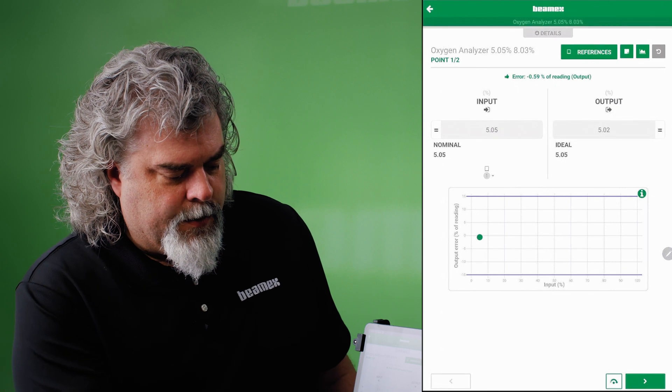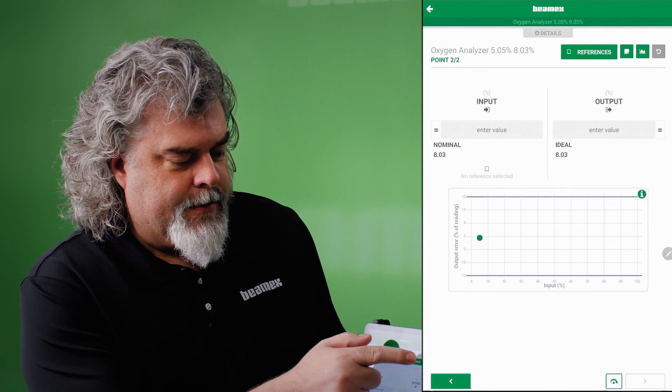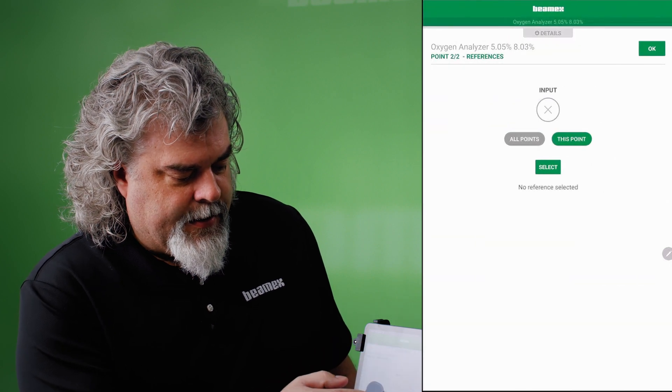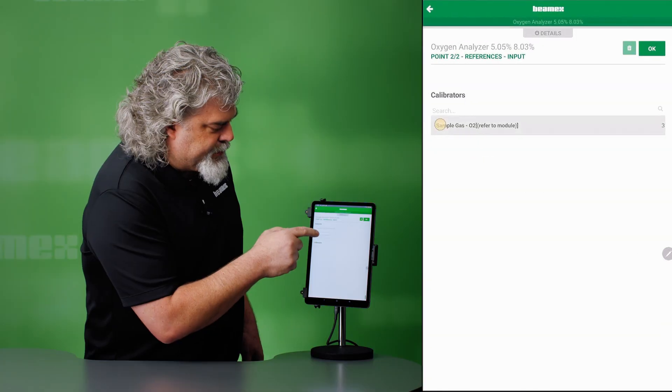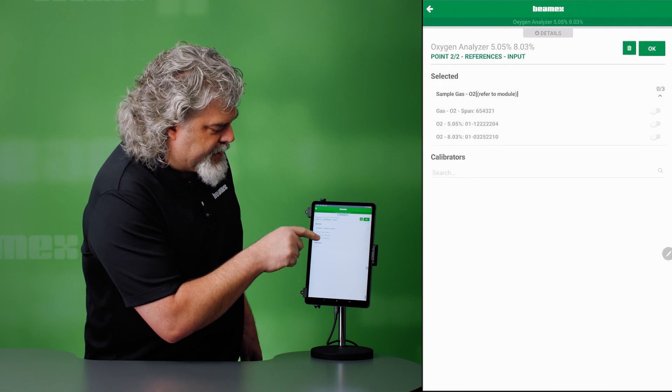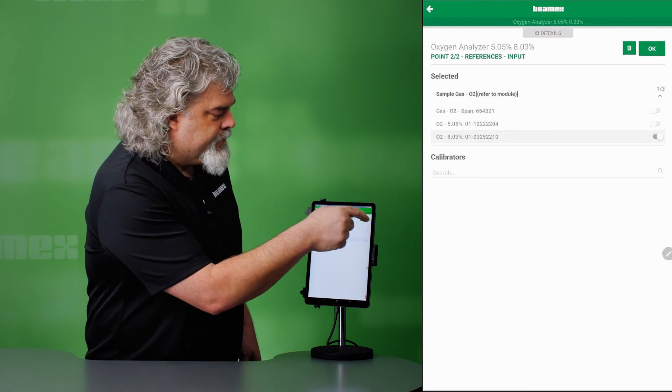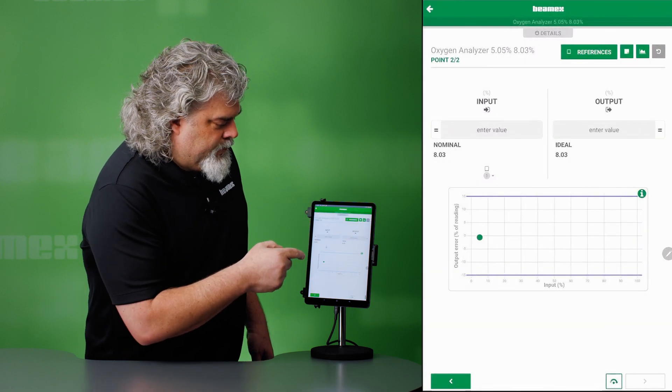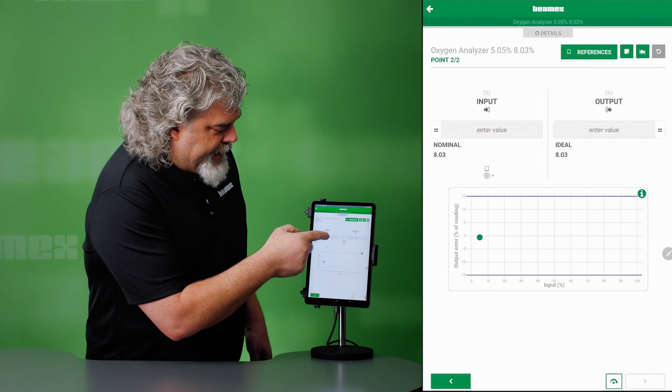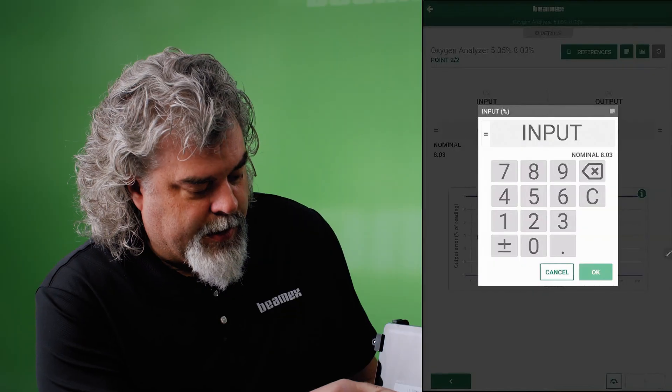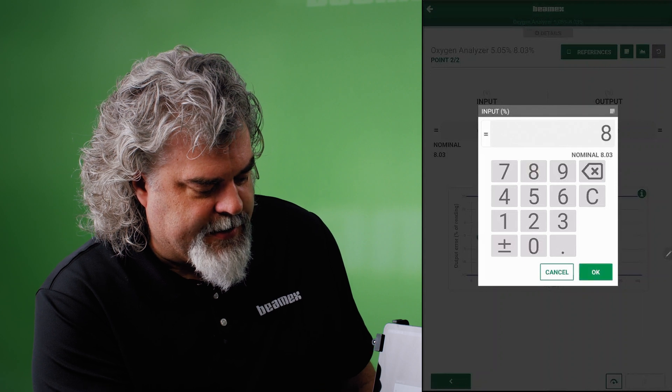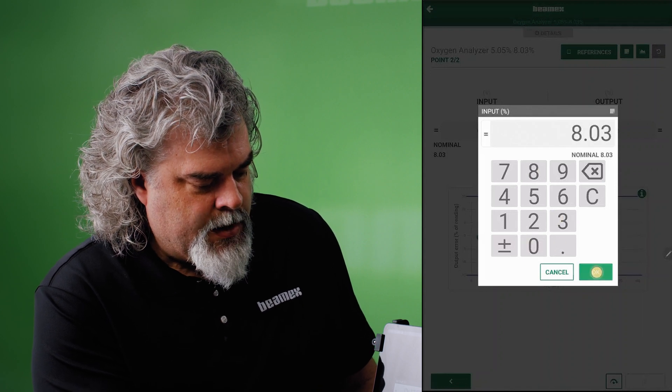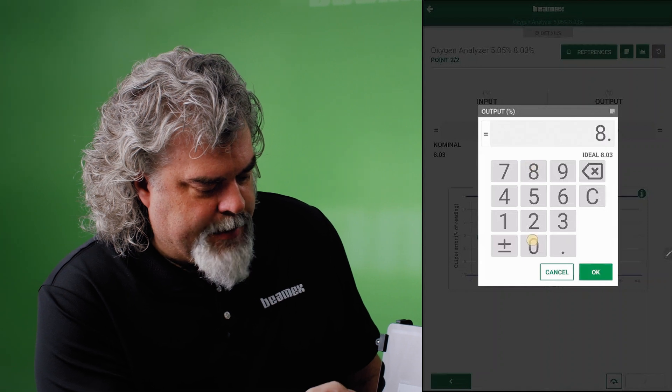We'll go to our next test point. That's 8.03%. Go to my references. I'll select my reference for this one specifically. So that's my sample gas here. And here's my 8%. Here we go. Reference done. Check. Now let's enter our next value. So our nominal here, we're expecting 8.03. That's what our gas is. 8.03. Our display, we're going to say is 8.01.